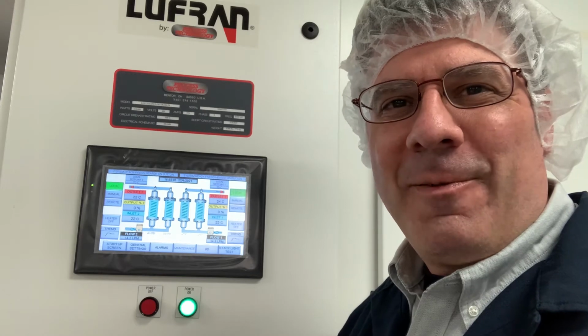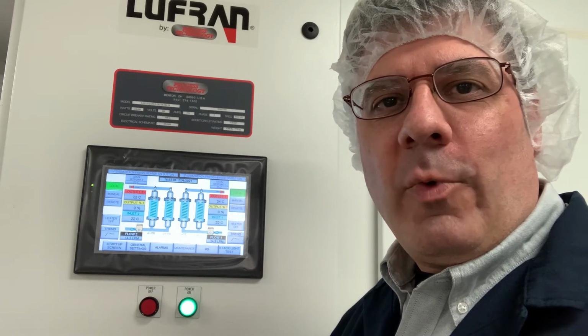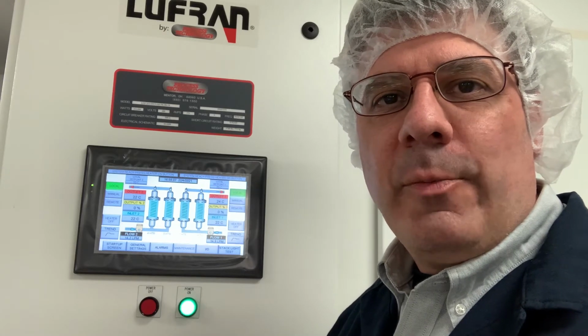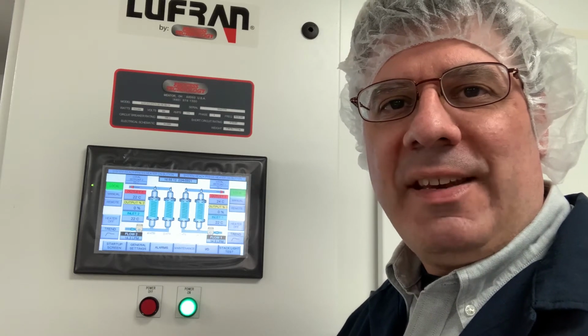I'm here in the high purity testing area to show you how to perform a flow calibration on a Lufran water heater. You'll want to perform the flow calibration either when your heater's new, or it has been moved to a new location, or you've replaced the flow meter. Aside from those instances, there shouldn't be a need to perform this procedure at all.